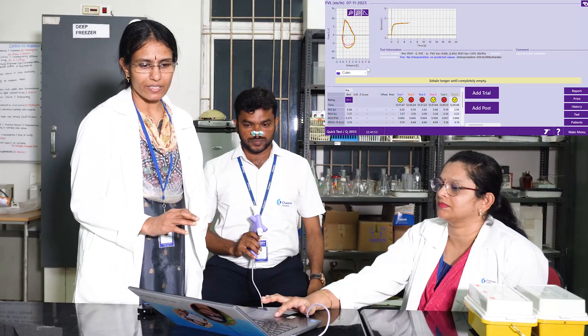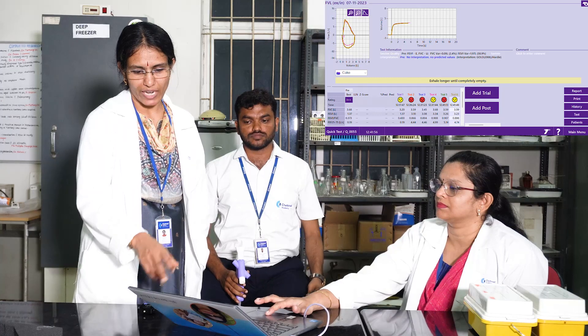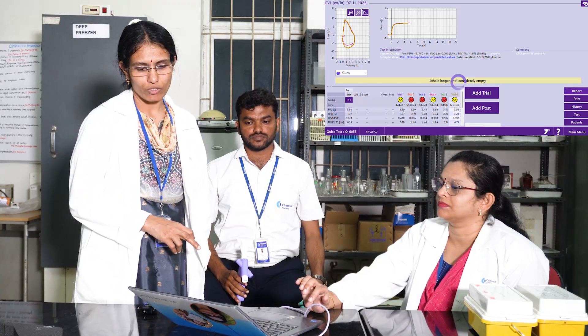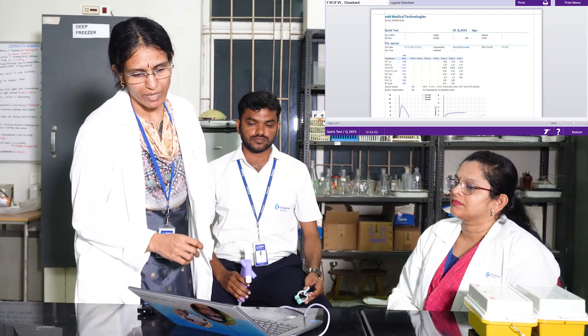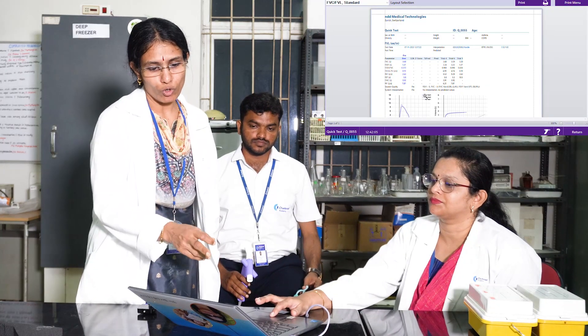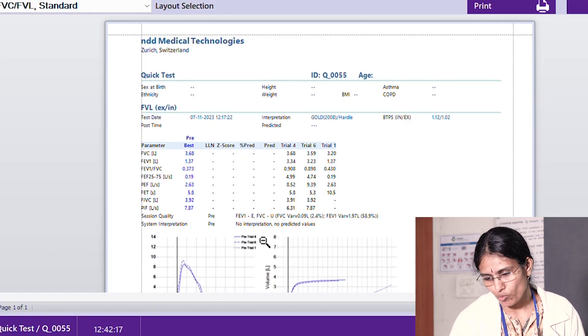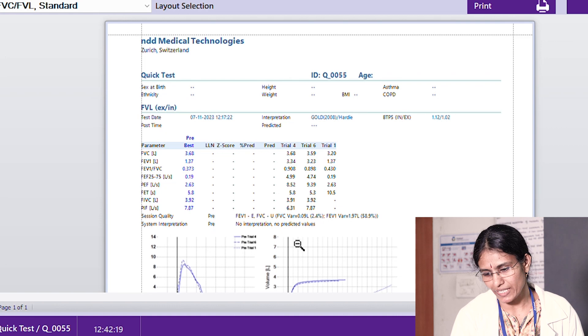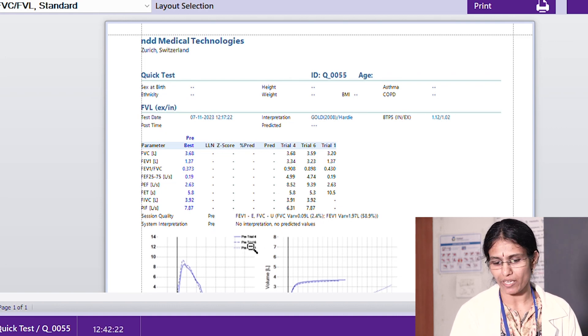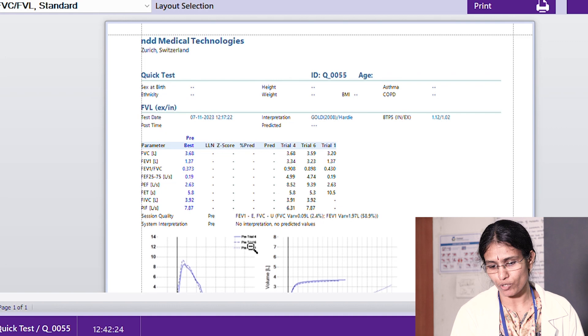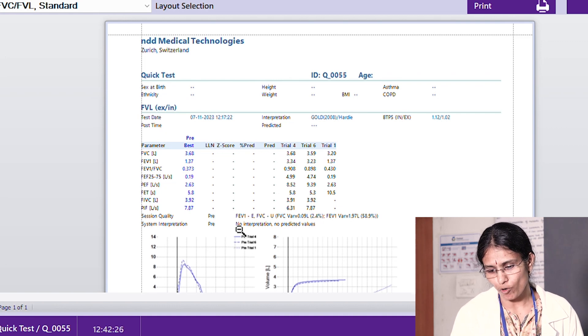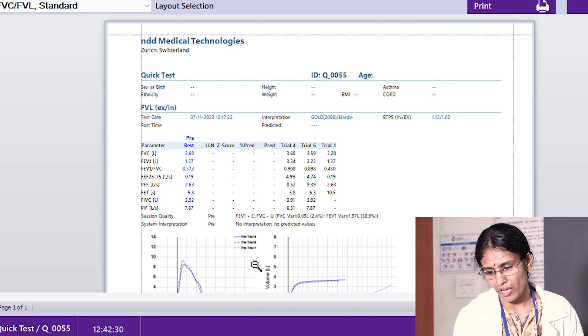You can do three trials and the best of the three can be taken, after which the report can be generated. This is the report. From the report, these are the values which can be interpreted. The forced vital capacity is 3.68 — that is the maximum volume of air expired during this manoeuvre. The forced expiratory volume in one second, the ratio, and the average mid-maximal flow can also be interpreted.